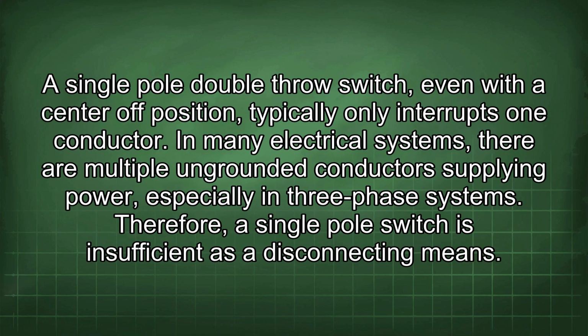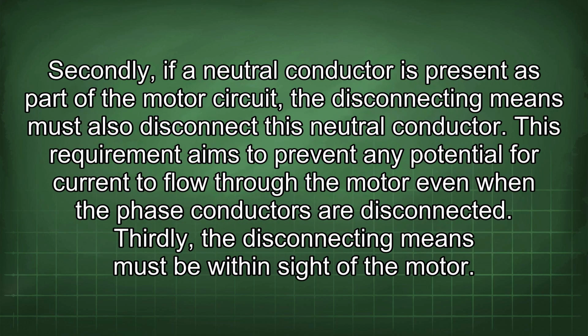A single-pole double-throw switch, even with a center-off position, typically only interrupts one conductor. In many electrical systems, there are multiple ungrounded conductors supplying power, especially in three-phase systems. Therefore, a single-pole switch is insufficient as a disconnecting means. Secondly, if a neutral conductor is present as part of the motor circuit, the disconnecting means must also disconnect this neutral conductor. This requirement aims to prevent any potential for current to flow through the motor even when the phase conductors are disconnected.